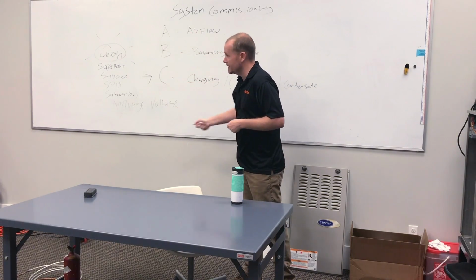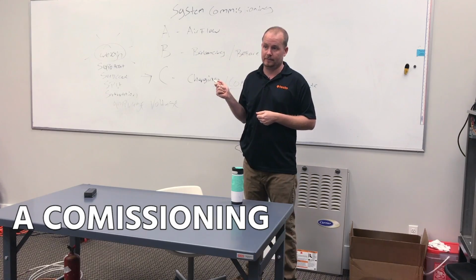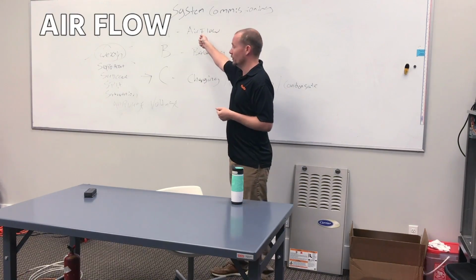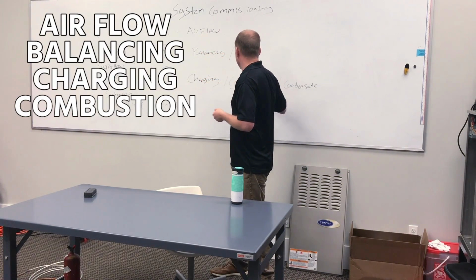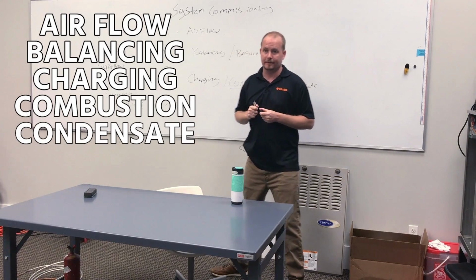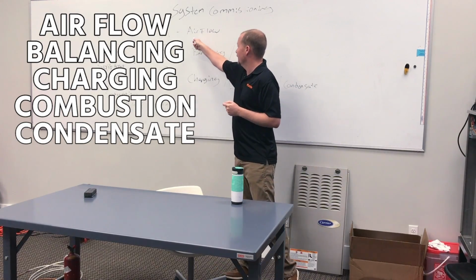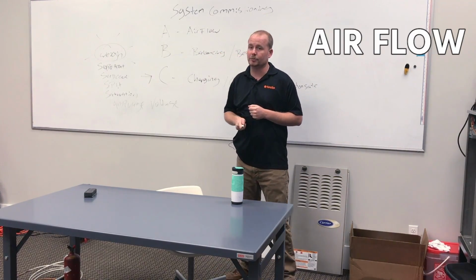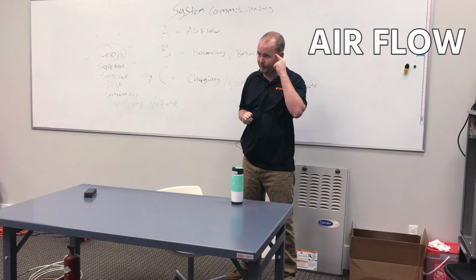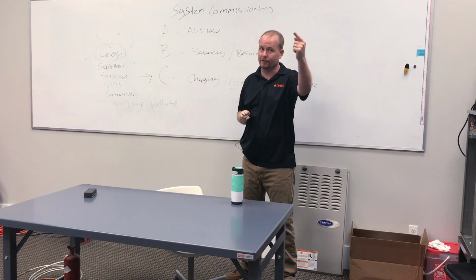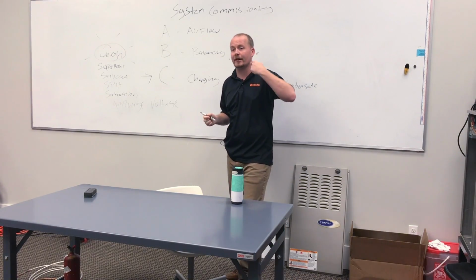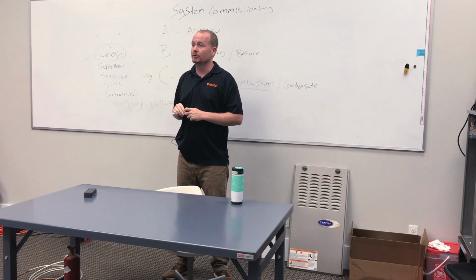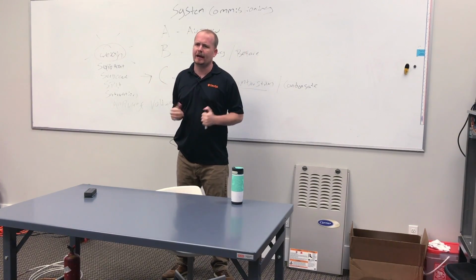That, my friends, is a commissioning. That's how you commission a system. Airflow, balancing, charging, combustion, condensate. ABC. But it starts with airflow. Starts with visual and auditory analysis of your airflow, moving into confirming that it's set up properly, moving into your static pressure checks. There's a lot of people who will say you should be actually checking airflow on every system.